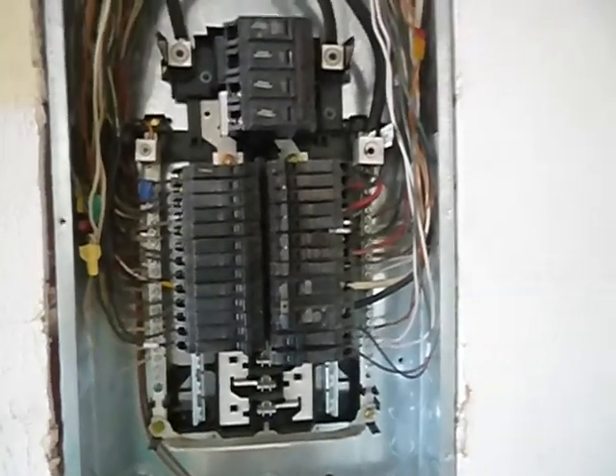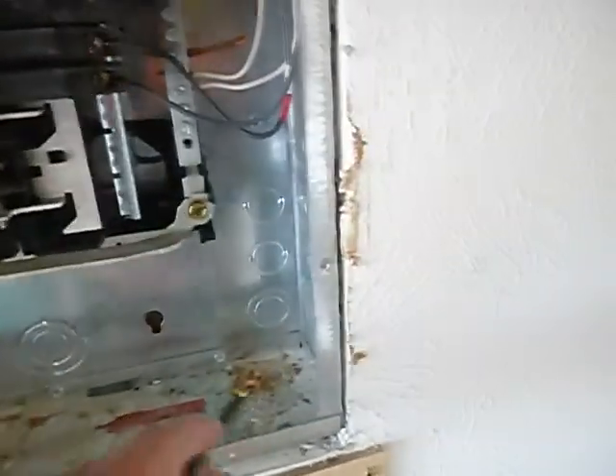I tripped that accidentally. I found these already tripped, so I'm not going to turn them on. That's for the exterior. That's why I'm not getting power on the fence. What else? That's about it. Oh, shouldn't have wood shavings in the cabinet. Gaps, wood shavings, bonding location, oversized breaker, white hots, no antioxidant paste. Woo-hoo. Screws, I already said screws.